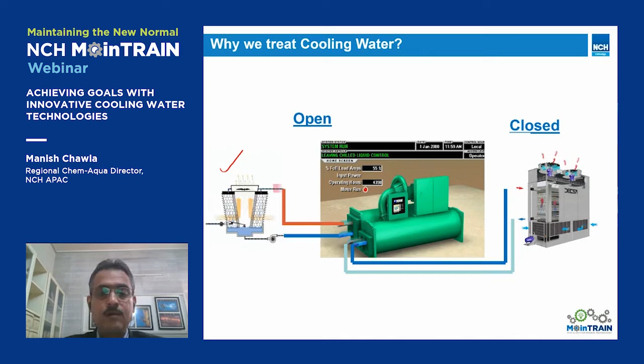At the same time, we might have a closed circuit, your chilled water going from the evaporator or cooler of your chiller to your AHU and coming back. Now the point is, the impurities which I mentioned, in open systems they will tend to concentrate. Why? Because how is the cooling taking place in the open cooling water system, in the cooling tower? It is by evaporation, right? So when water evaporates, it takes the latent heat of vaporization, so the remaining part of the water gets cooler.